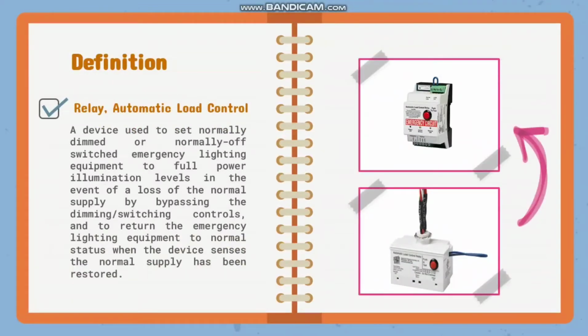Next is Relay Automatic Load Control or ALCR, a device used to set normally dim or normally off switch emergency lighting equipment to full power illumination levels in the event of a loss of the normal supply by bypassing the dimming or switching controls and to return the emergency lighting equipment to normal status when the device senses the normal supply has been restored. So, the ALCR ensures a light-on state during loss of normal power while tracking the state of normal lighting loads during normal operation. So, ito yung itsura niya.